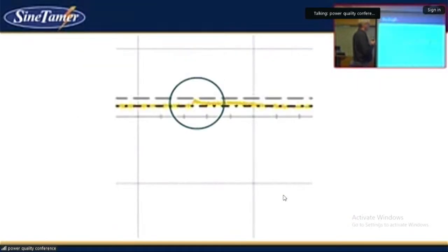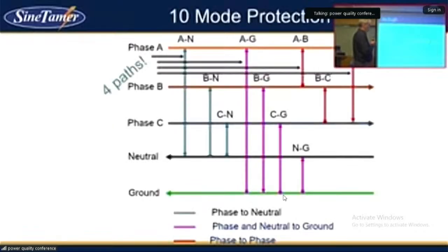These are the 10 modes of protection. There's 3 between the phases. You've got 3 phases and neutral, that's another 3. And 3 phases and ground, that's another 3. Then between ground and neutral, making up the 10th mode of protection.